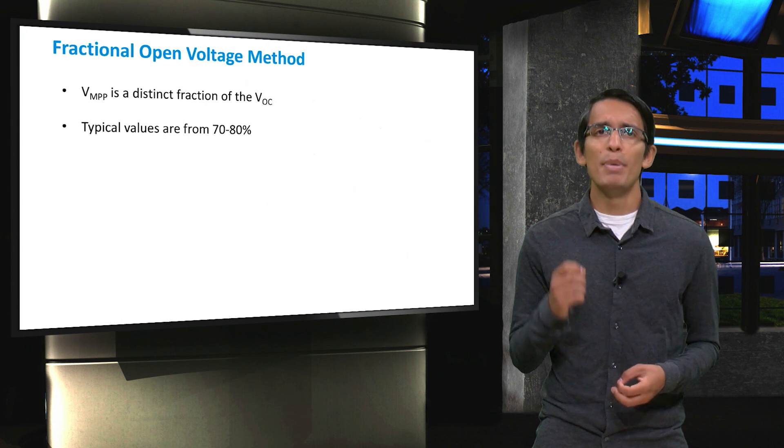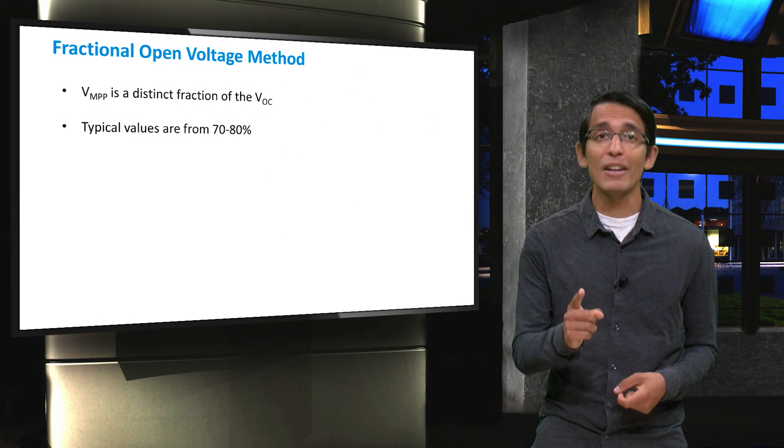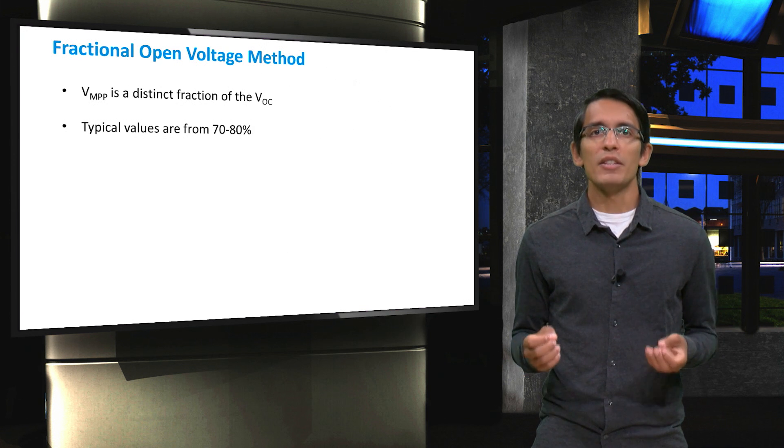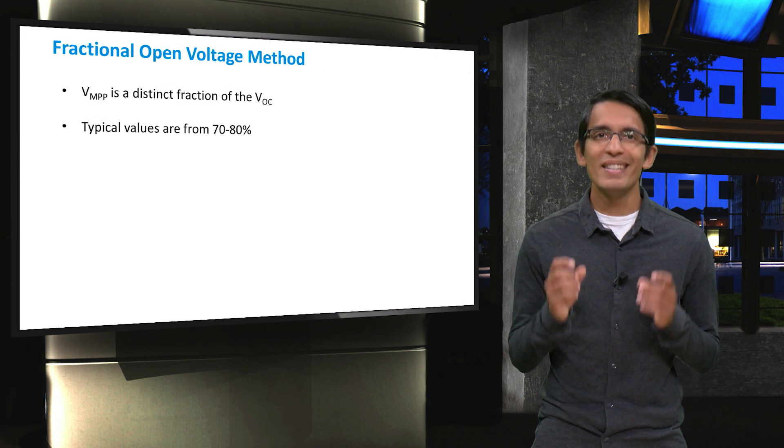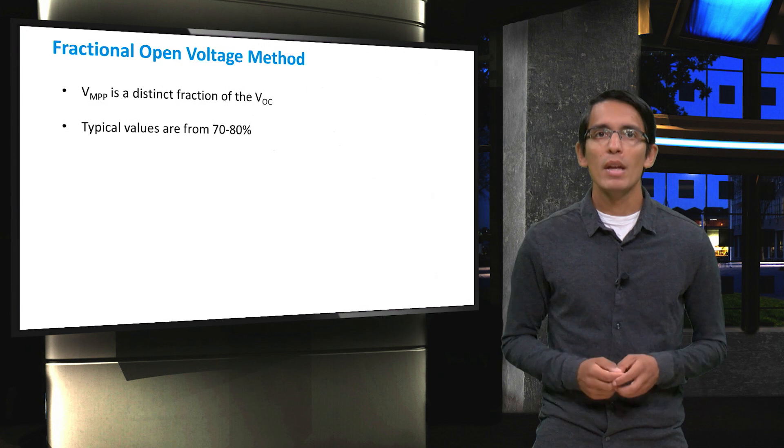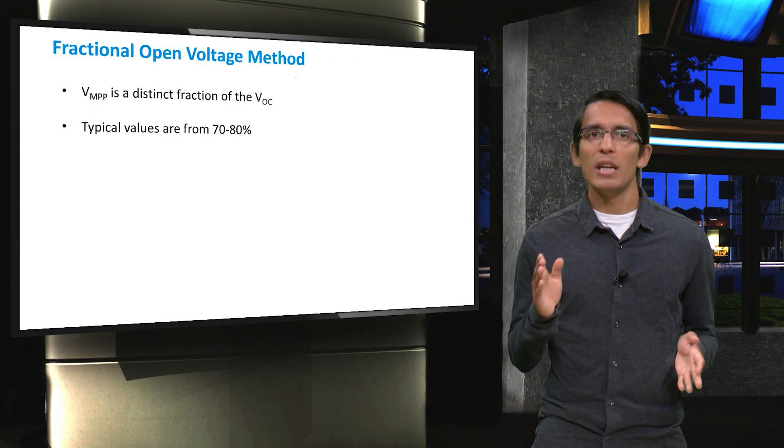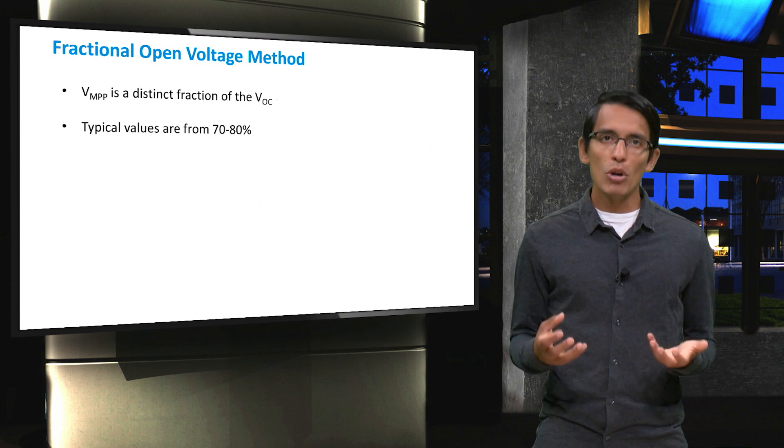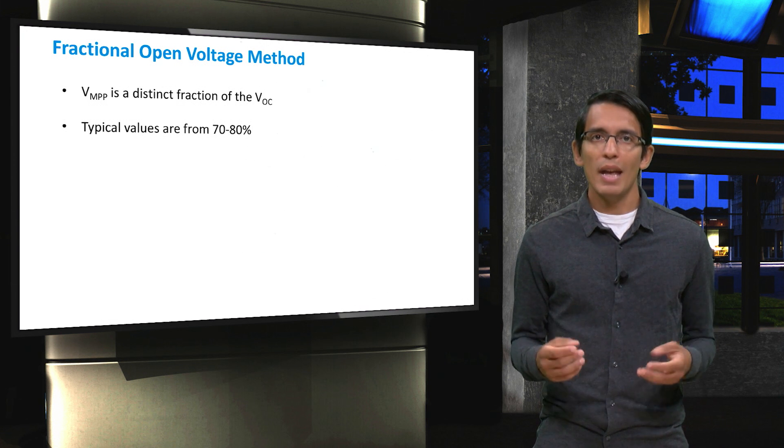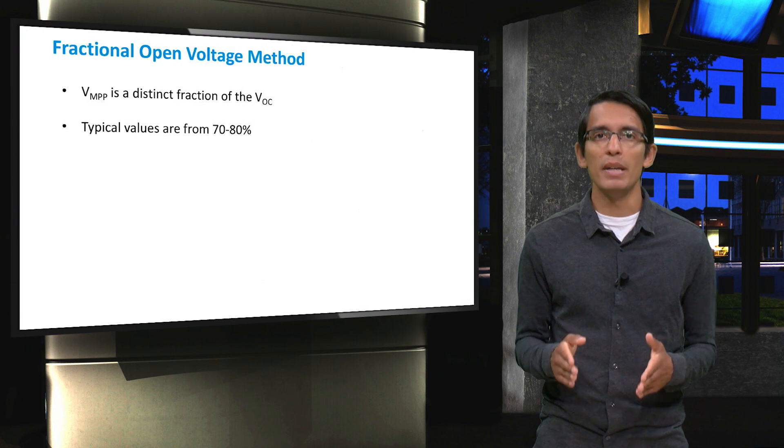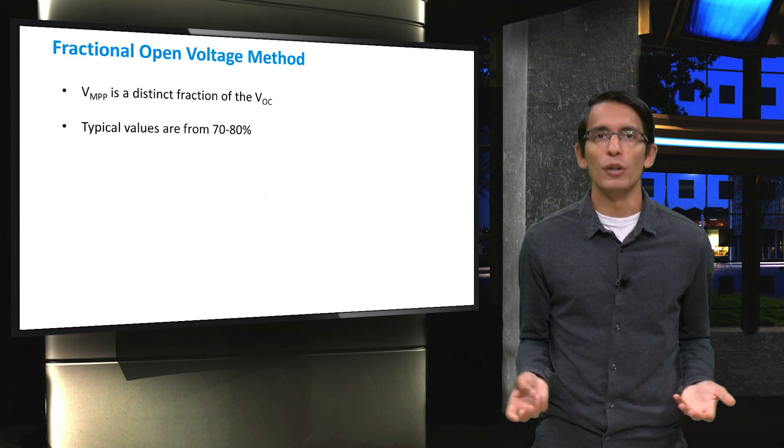The next technique adds a bit of complexity and is known as the fractional open voltage method. Here, we make the assumption that VMPP is a distinct fraction of the open circuit voltage of the PV panel or array. The value used here is usually between 70-80% of the open circuit voltage. This method is a bit more robust than the constant voltage method as the VOC will scale at approximately the same rate as the VMPP, thus making it more suitable for panel degradation and different illumination conditions.